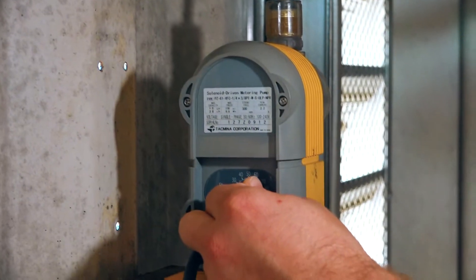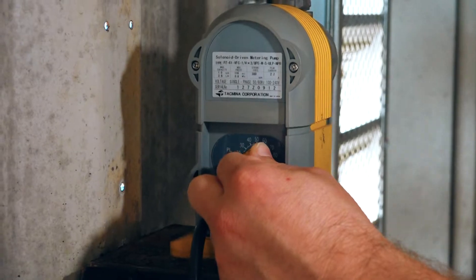Get a water analysis done — have a professional company come in that can analyze the water, your boiler water and your makeup water, and tell you what kind of chemicals are needed. Have a dosing pump installed, get the chemical in and have the rate set, and then your water chemist can also tell you the preferred blowdown rate at that point.